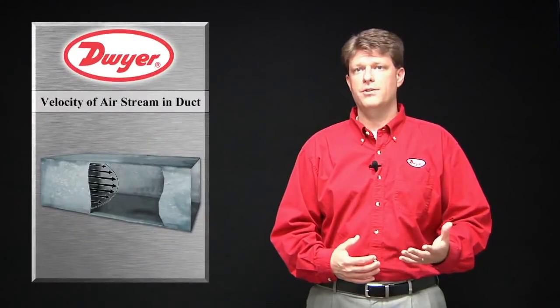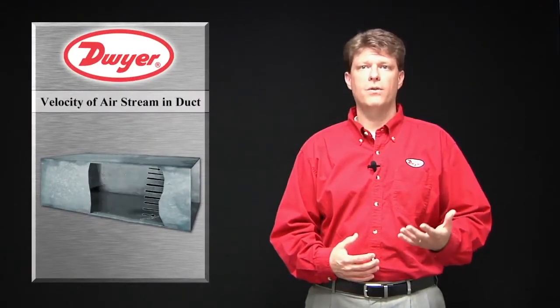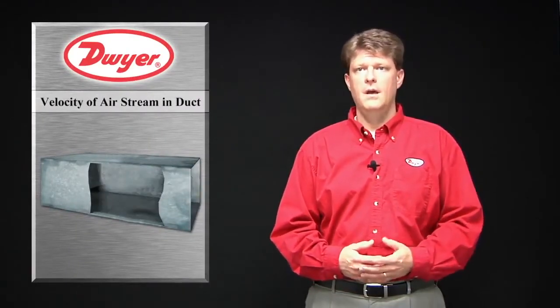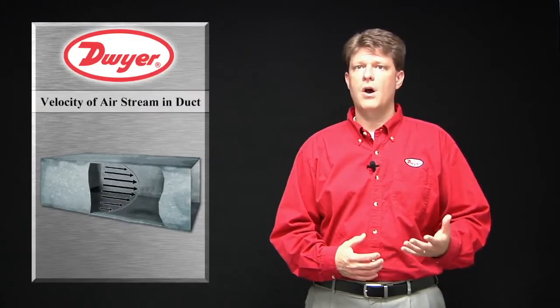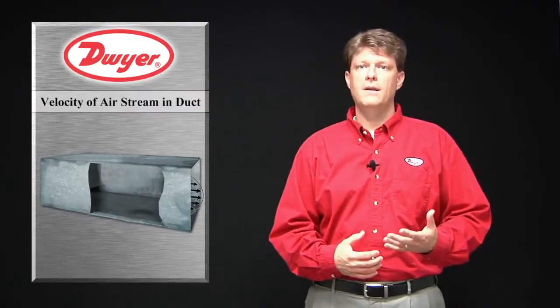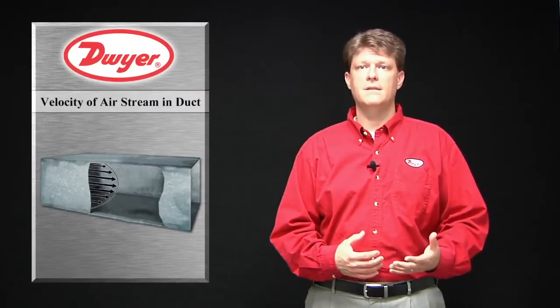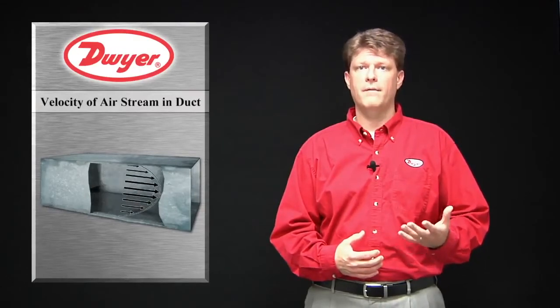The velocity of the airstream in a duct is not uniform over the cross-section of the duct. Friction against the duct walls causes the air velocity to be lower near the sides than the velocity in the center, creating a parabolic velocity profile as shown.